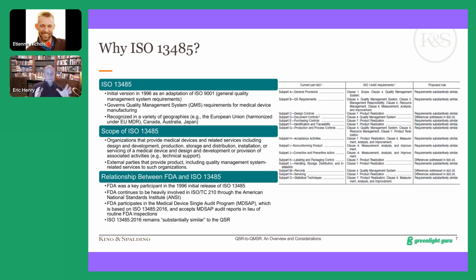So 13485, as I mentioned earlier, was initially released in 1996, and it was an adaptation of the ISO 9001 standard specifically for medical device companies. And it primarily drives the establishment and the use of a quality management system for medical device manufacturing, and it's recognized around the world. In fact, in the European Union, it is one of the harmonized standards under the EU medical device regulation. So where the EU medical device regulation, the MDR, requires quality management system establishment and execution, they consider ISO 13485 to be the state-of-the-art standard that shows compliance to those expectations.